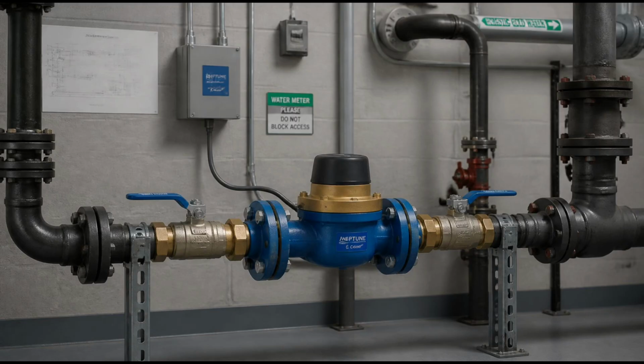The first is the main shutoff valve. This valve exists for a simple but essential reason. It gives the building the ability to isolate itself from the municipal supply. In the event of a major leak, a burst pipe, a flood, or any emergency that requires the water to stop flowing, this valve is the mechanism that makes it possible. One action, turning the valve closed, and the entire building's supply is cut off at the source. No water continues to enter. Whatever pressure remains in the pipes bleeds away as fixtures are opened, and the system can be safely worked on.